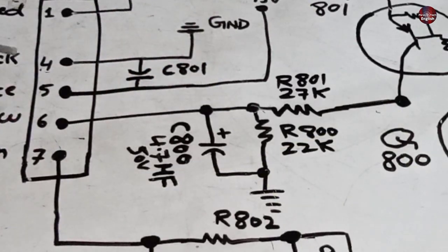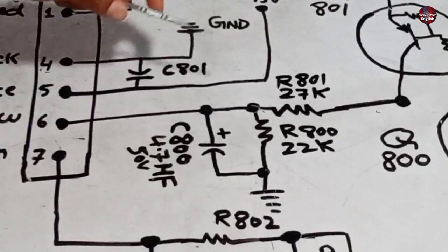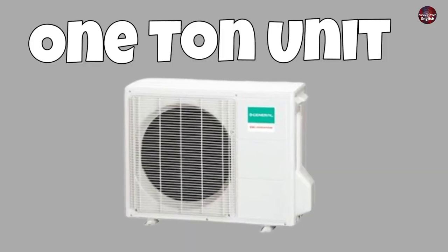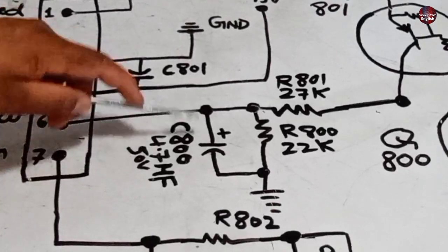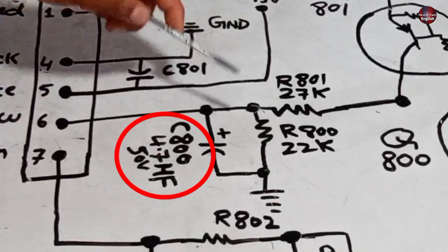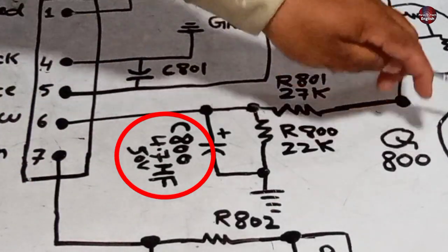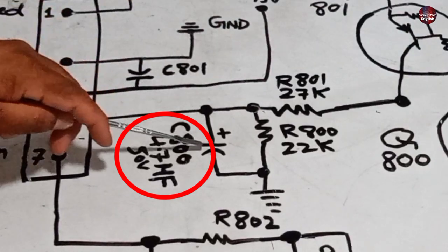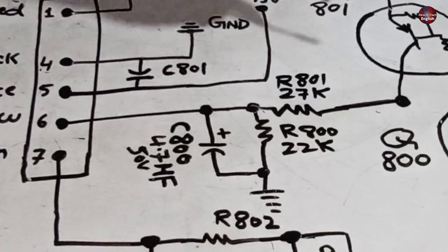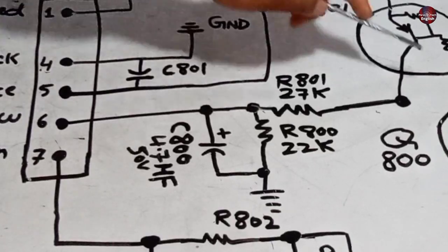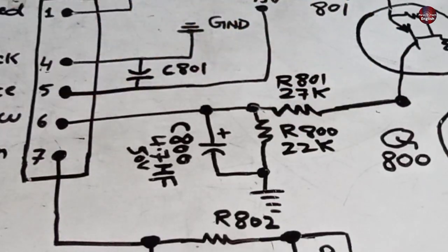In this model, they have used fewer components because this is a 1 ton mini split AC, which is why the fan circuit is designed this way. And here, the capacitor C800 of 4.7 microfarads and 50 volts is installed, and if it is short-circuited, still the fan will cause problems. Because when the operating voltages will pass through the capacitor, it will not work properly due to getting short-circuited.